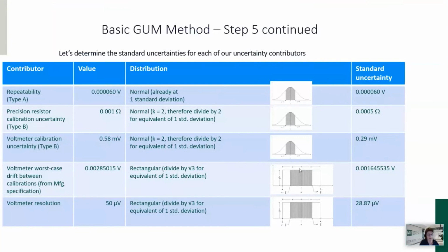So for the probability that they fall within the extreme portions of these limits, we just assume the worst case and think that it's equal. And for that, to make a rectangular distribution equivalent to the standard deviation of a normal distribution, we divide by the square root of 3. I'm sorry, we don't have time to derive that right now, but take my word for it. You can look it up in the GUM and the other guides that go into this a little bit deeper. So we take this value, we divide it by the square root of 3, and we come up with this value.